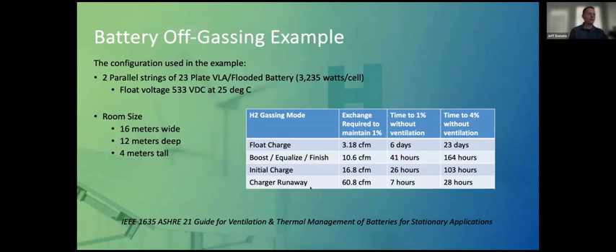If something is left on equalized charge, then of course it takes obviously a lot less time, but we're still talking hours. So this is not so much a leak detection kind of example, but more of a slow, gradual buildup. And then you can see how much time it would take to get to 4%. Again, these are referencing the IEEE document. And you can run these examples yourself by using that document, based on the room size, the amount of ventilation that currently exists, and the battery type.